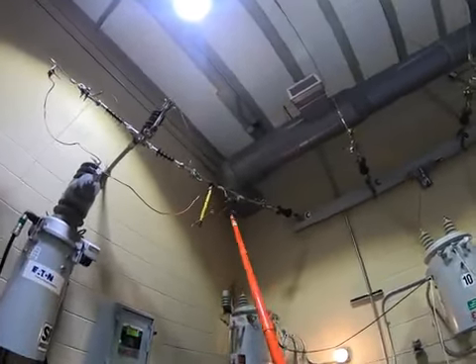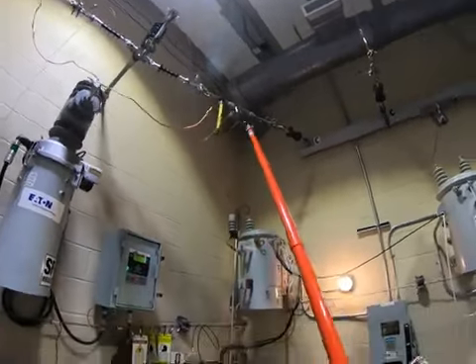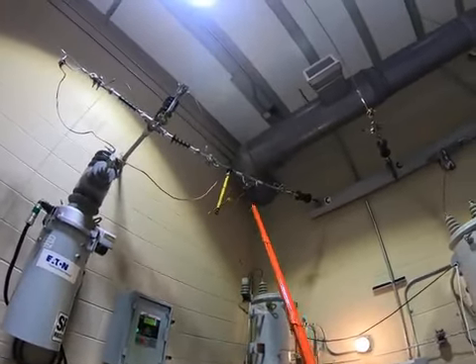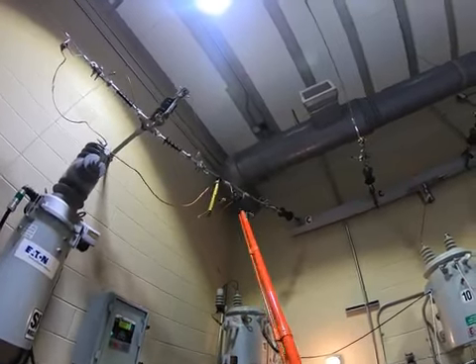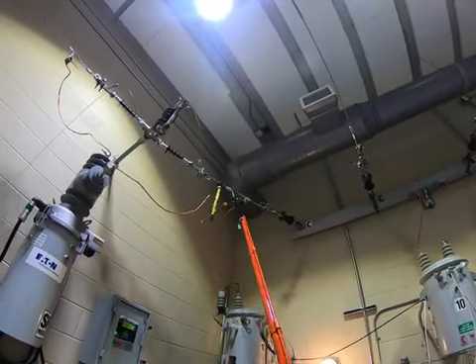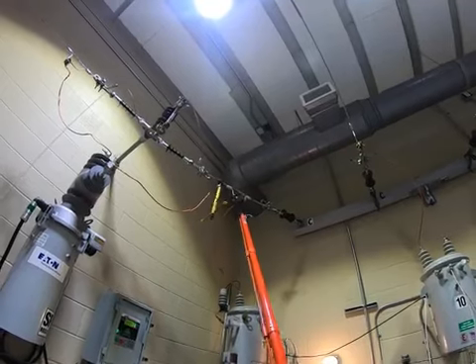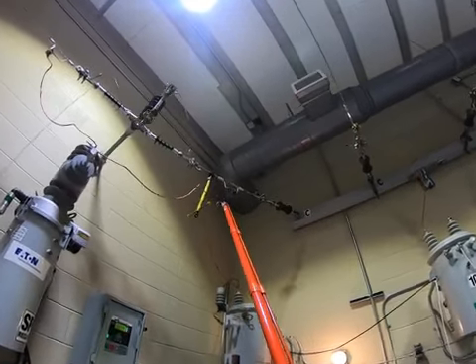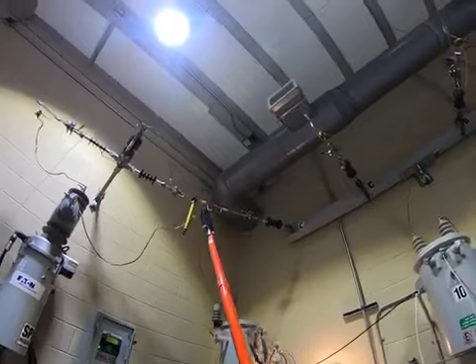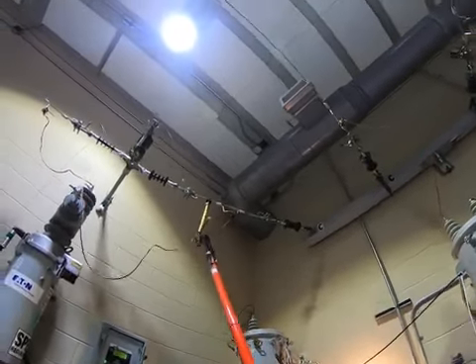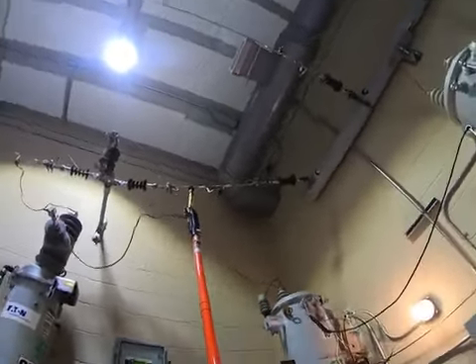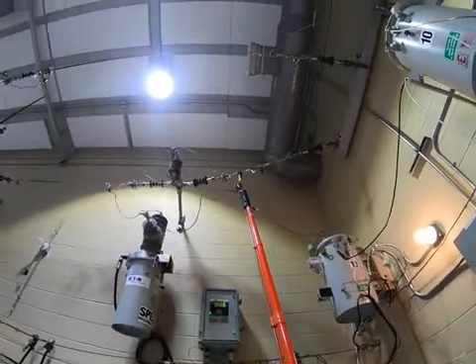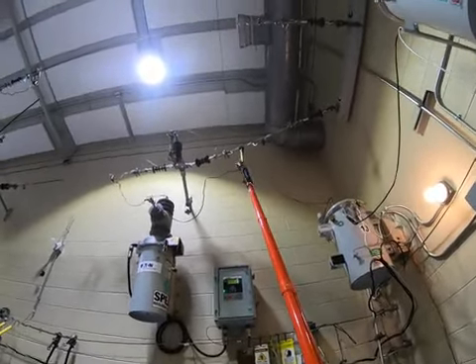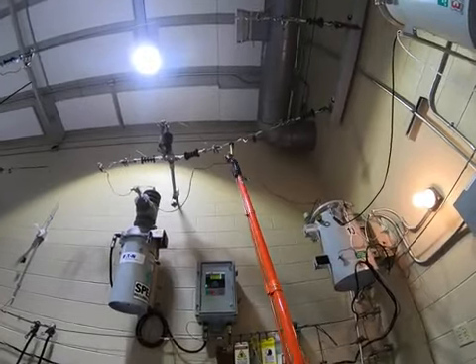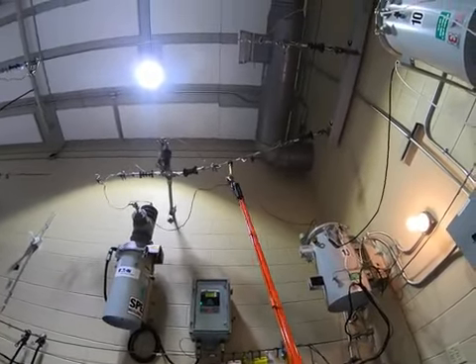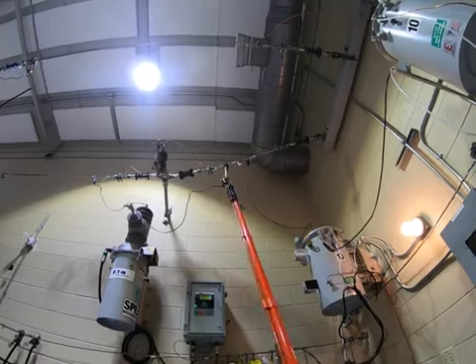So in the hot lab, what we've been doing for years is using this yellow insulated T standoff. I'm not 100% sure what the technical term for it is, but it's an insulated standoff, jumper holder I'll call it. What we've been doing, so students don't have to worry about dropping it, is putting this right on here and then just pinning it there. The reason we do that again is in case those contacts really didn't close or open, we want to make sure that jumper doesn't fly into anything because it would still be hot.